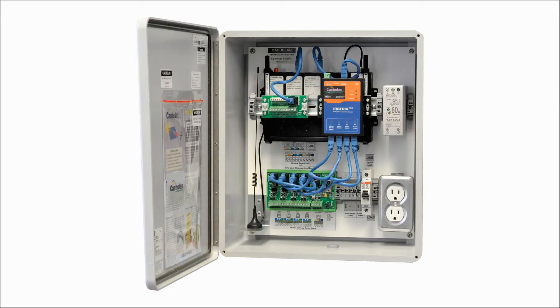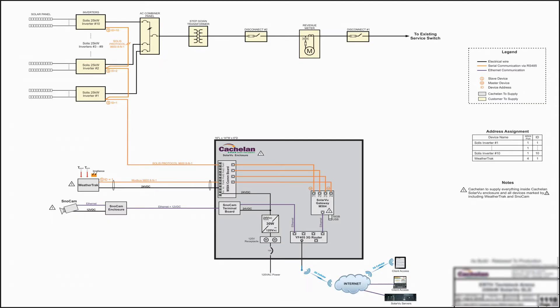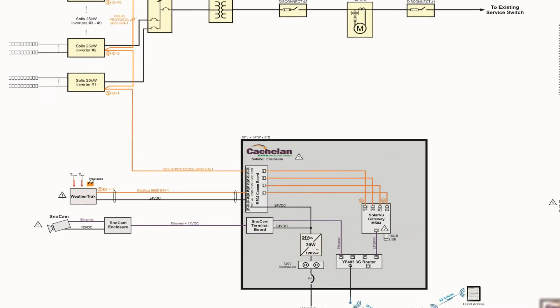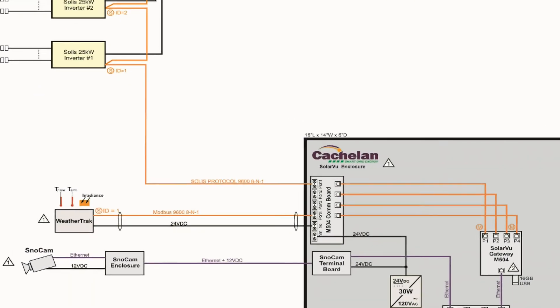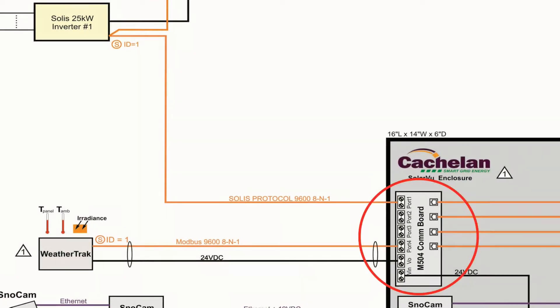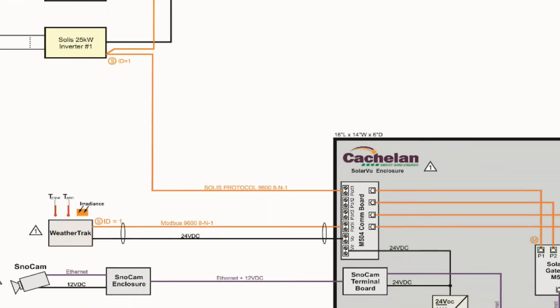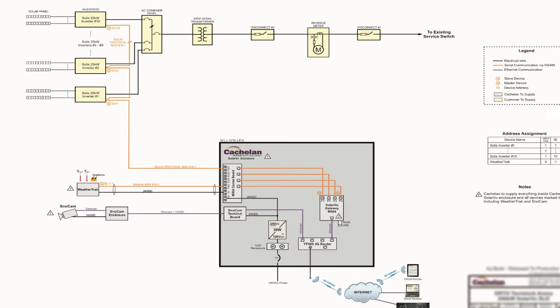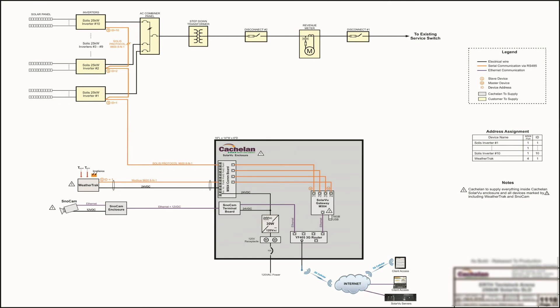Within the SolarVu enclosure, there is a document pouch attached to the inside of the door, which contains documents relevant to the specific site. Among these documents, there will be a single line drawing, which displays the port that the inverters should be connected to on the COM board. In this case, it's port 1. I would advise that you hold on to this drawing, since it will be useful later on in the video when we are setting slave addresses.